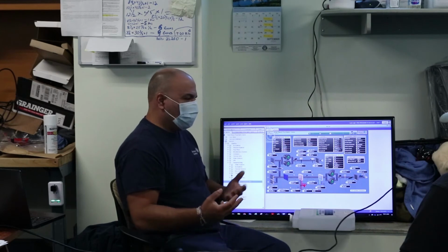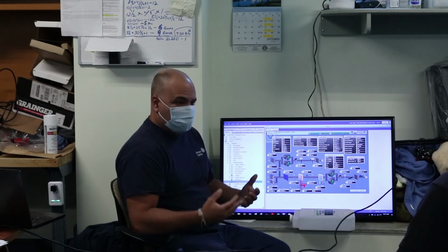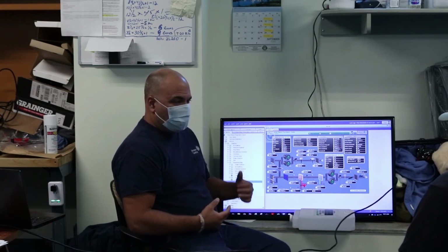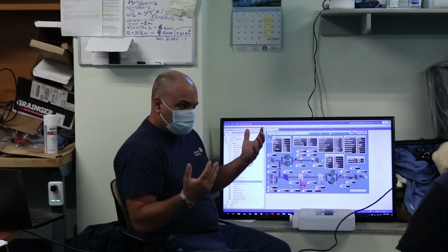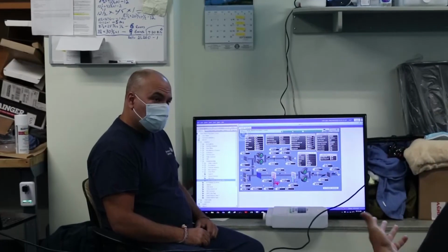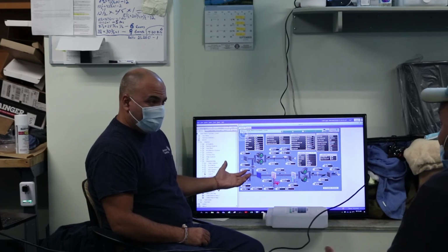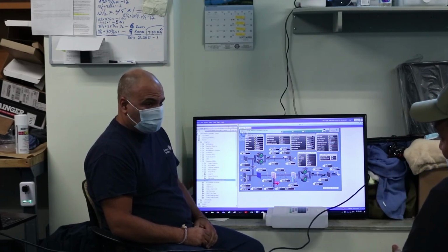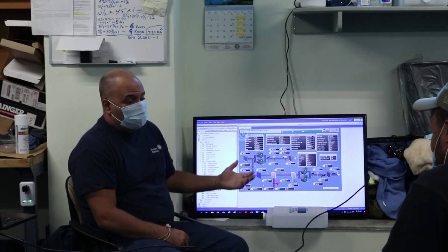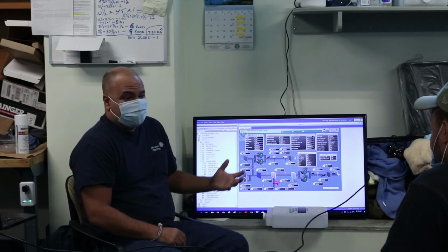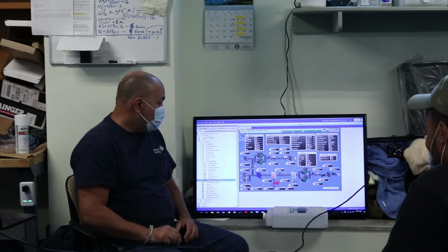You guys are more like a hospital. If it was an office building, it would be so many CFM per person, whereas a hospital environment is more air changes. It's not a bad thing. It's tough in the summer when you bring it in at 60%. That's hot, wet air, right? Yes, that's the problem with the building. But in wintertime, fresh air is a good thing, though you're going to be using a lot of energy. And we've got no chillers.